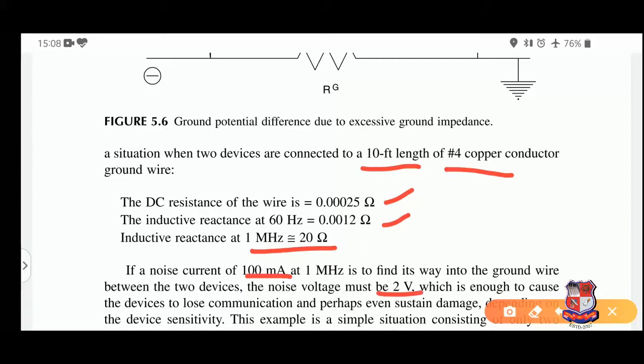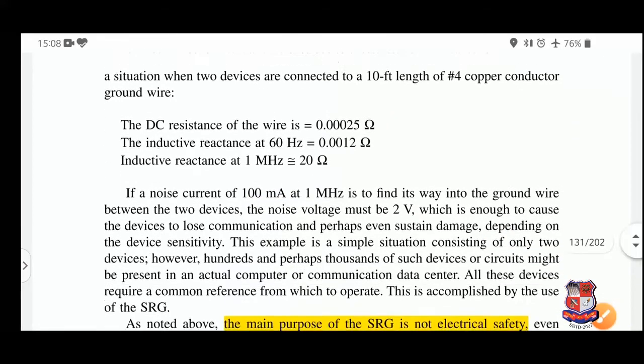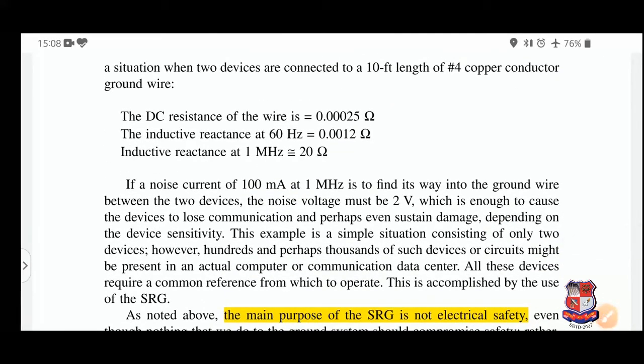A noise voltage of 2 volts is enough to cause the device to lose communication and perhaps even sustain damage, depending on device sensitivity. This example is a simple situation consisting of only two devices. However, hundreds and perhaps thousands of such devices or circuits may be present in an actual computer or communication data center. All these devices require a common reference ground from which to operate — accomplished by the use of SRG.